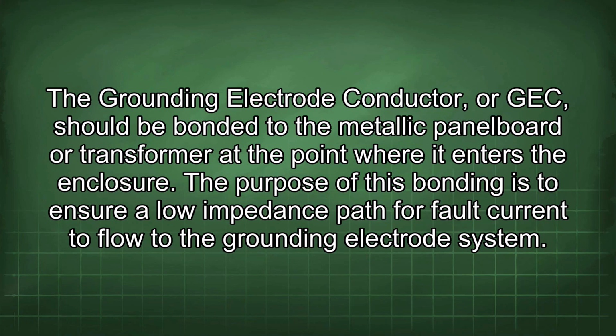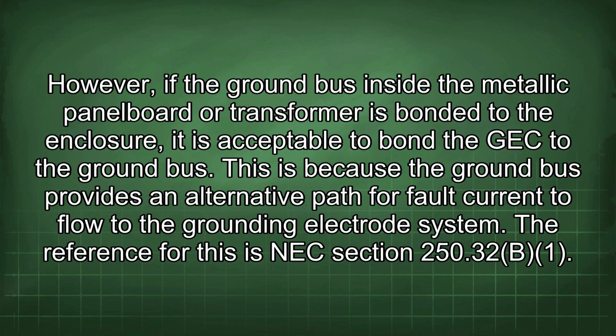The grounding electrode conductor, or GEC, should be bonded to the metallic panel board or transformer at the point where it enters the enclosure. The purpose of this bonding is to ensure a low impedance path for fault current to flow to the grounding electrode system. However, if the ground bus inside the metallic panel board or transformer is bonded to the enclosure, it is acceptable to bond the GEC to the ground bus. This is because the ground bus provides an alternative path for fault current to flow to the grounding electrode system. The reference for this is NEC section 250.32.